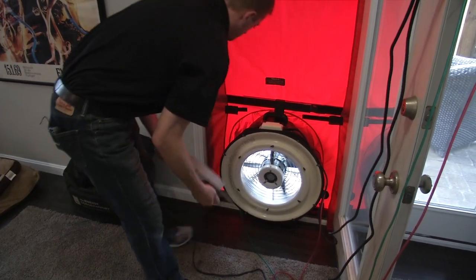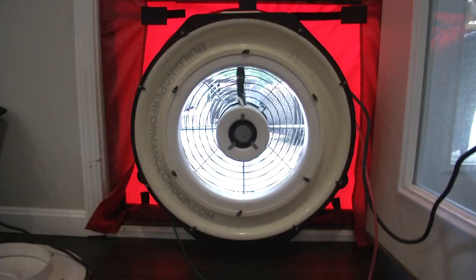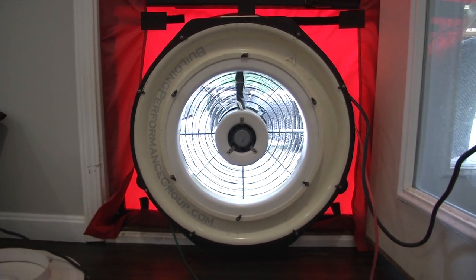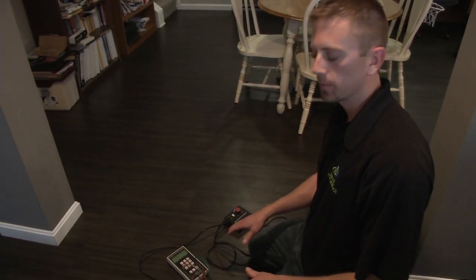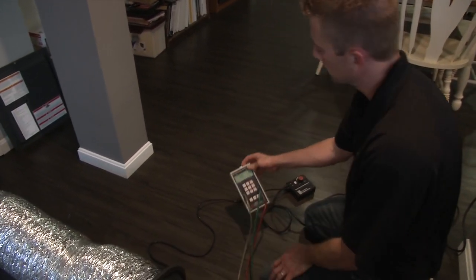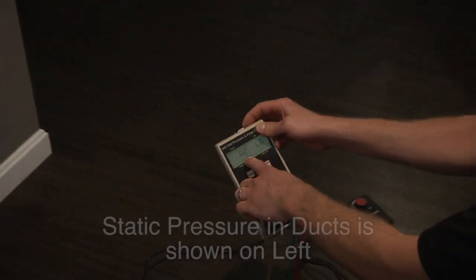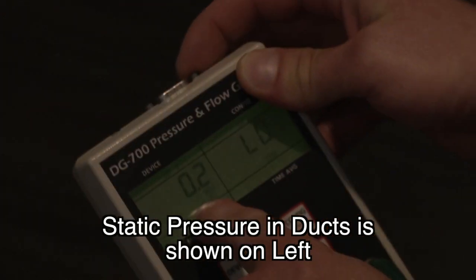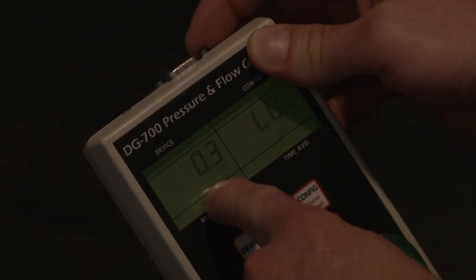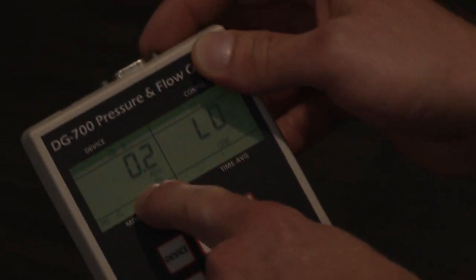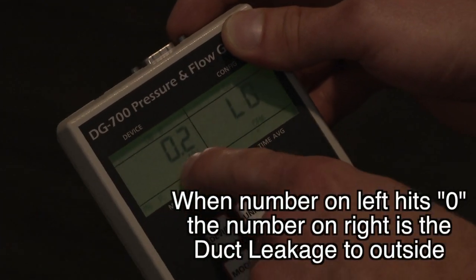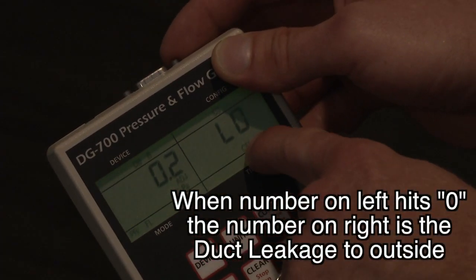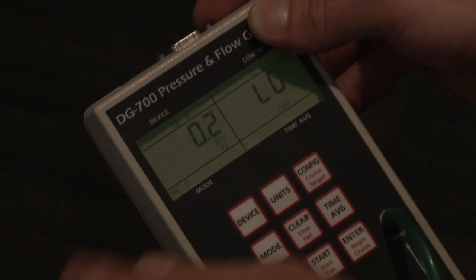Now we got the blower door, it's ramped up, it's created a pressure difference of 25 pascals on the house. Duct Blaster set up. I'm looking at my pressure gauge here. This number on the left is the static pressure in the duct system that's being created with the blower door. I need to make that number hit 0, and whenever that number hits 0, the number on the right is my duct leakage to outside.